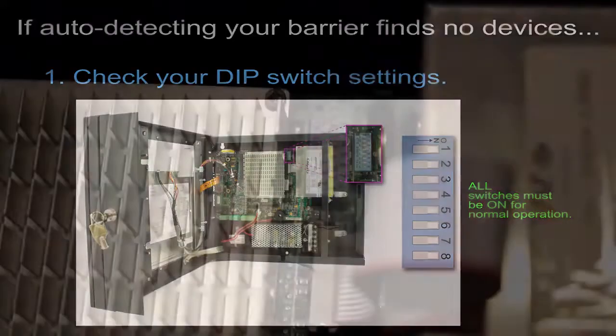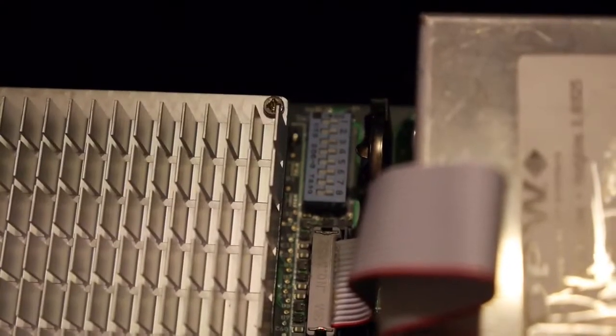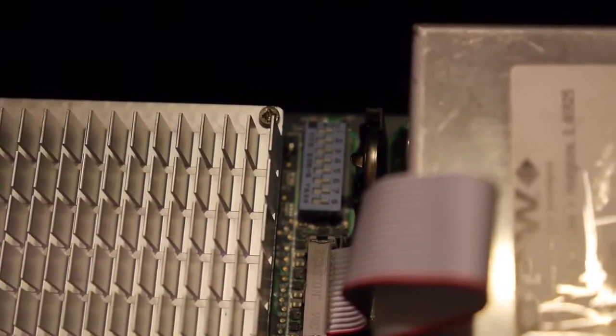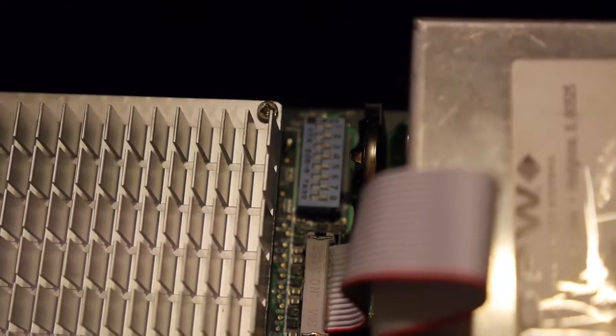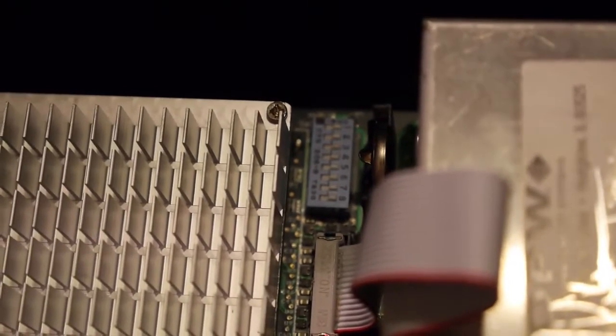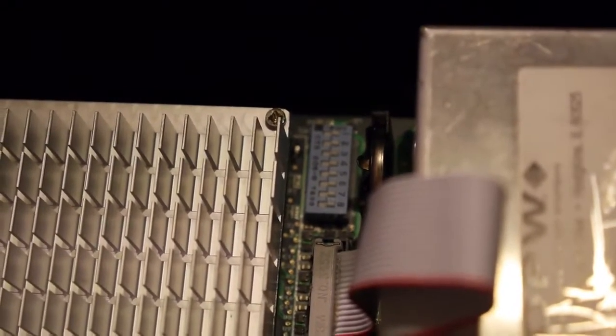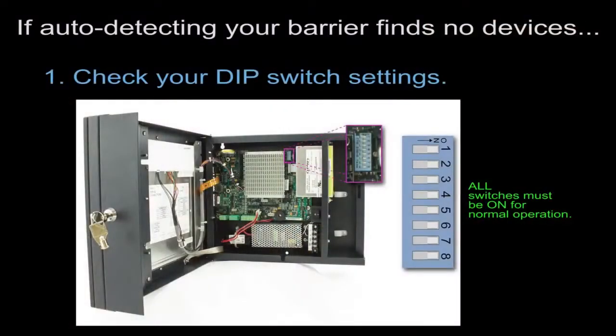The biggest problem that we're seeing is that the internal dip switch number 3 has been flipped to the off position. Basically what you need to do is just power down the system, flip that back to the normal position where all of them are in a line, and go ahead and do the auto detection again.